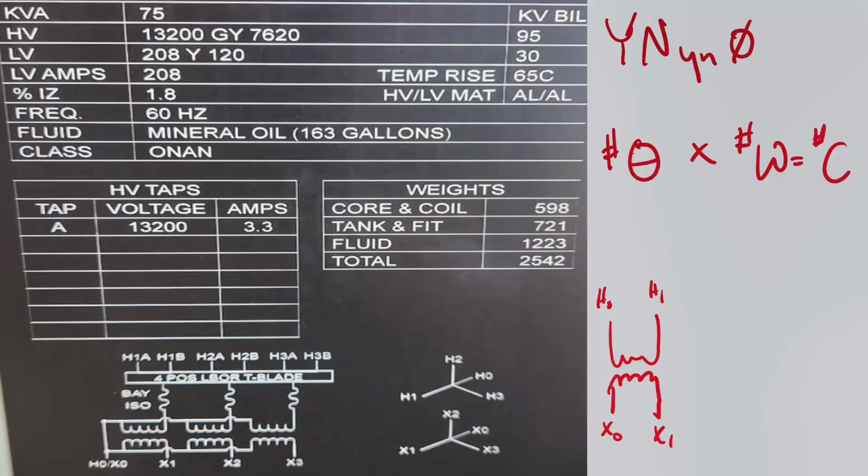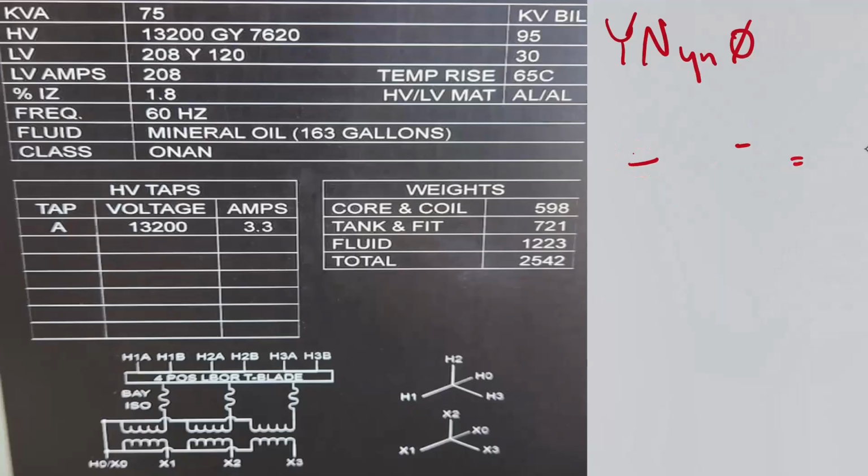So if you remember that, you can always look at this and figure it out. Another cool trick that you can do, don't look at this neutral. That'll get you wrong every time. But look, you have 1, 2, 3, 4, 5, 6 right here. And this vector diagram is a direct representation of how it's supposed to, in a way, superimpose from one vector or one winding to the other. So given that knowledge, this is a Y to a Y. If you just remember that we're going to have neutral voltages on both of these, then what we're talking about is a phase to ground voltage from here to here, right? And so that means that both of these get a phase to ground voltage.